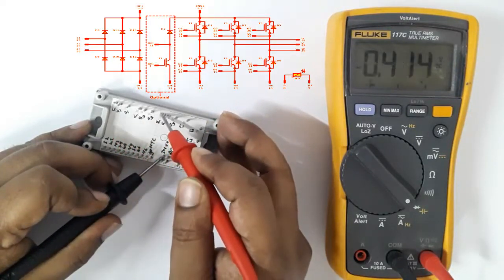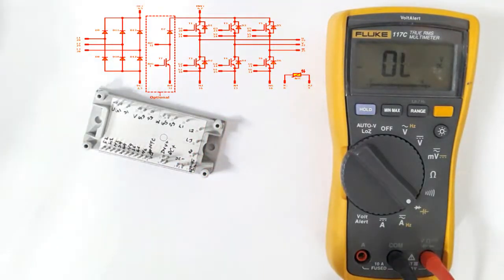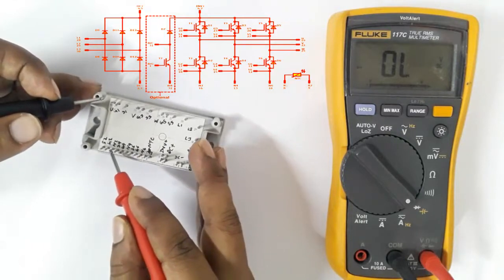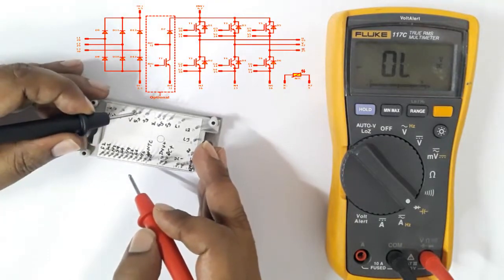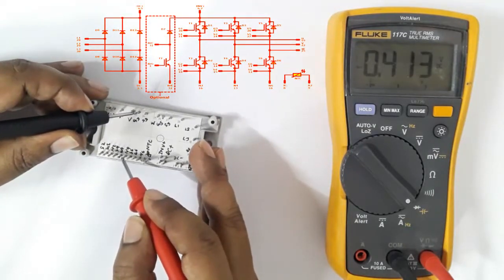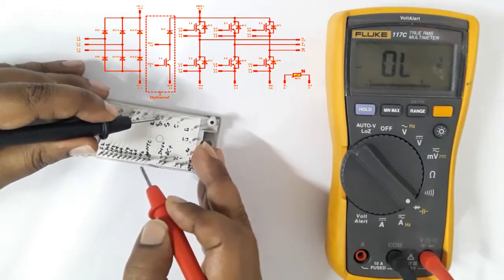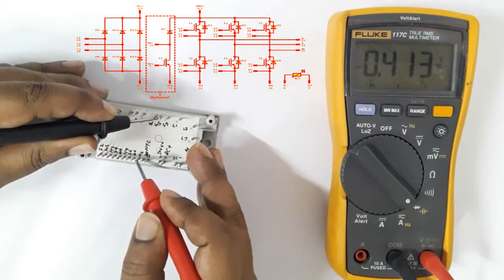V and W also about 0.4 volts DC. Now testing the negative terminal. For U terminal, the negative terminal is here, set red probe. For terminal V, negative terminal is N4. For terminal W, negative terminal is N6. All about 0.4 volts DC.